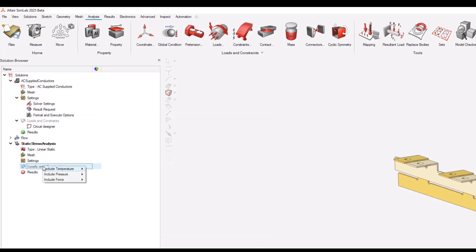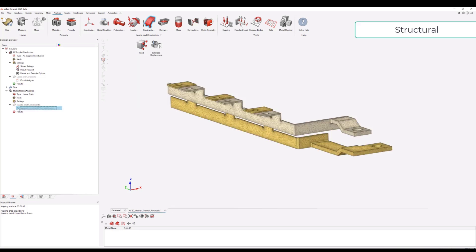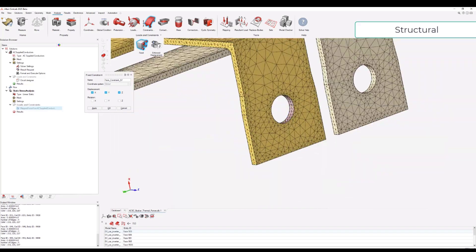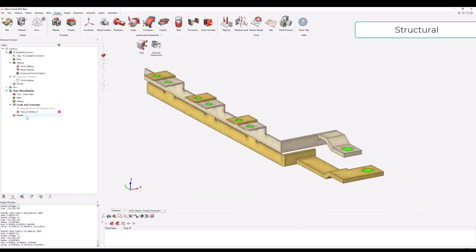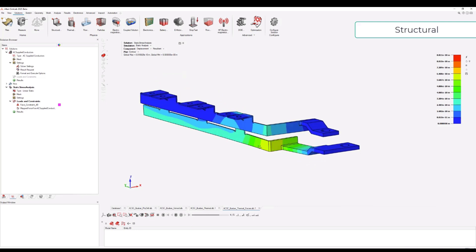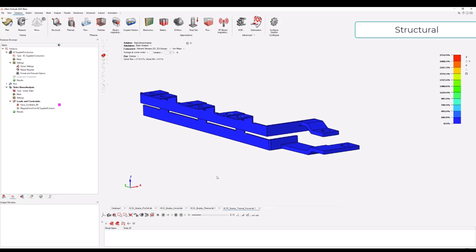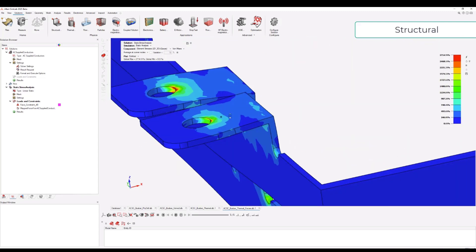That's confirmed. Then under loads and constraints, we right-click and include force from AC supplied conductors. This force will be mapped and applied as a load on our structure. We can then add boundary conditions such as fixed points - quickly selecting all the connection points of the busbars and making them fixed. We can update the results, which takes just one or two minutes. As a result we can see displacement due to the force and also the stress applied on the structure. In the event of a short circuit with a very high current, this is how you look at the maximum stress creating potential failures in your busbars. We can see stress concentration on the borders next to the connection points.